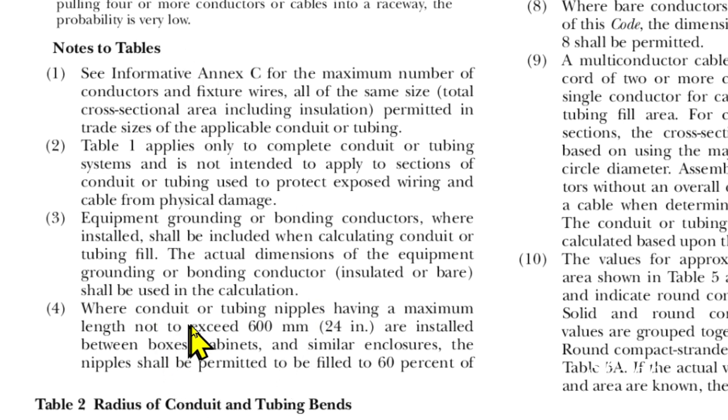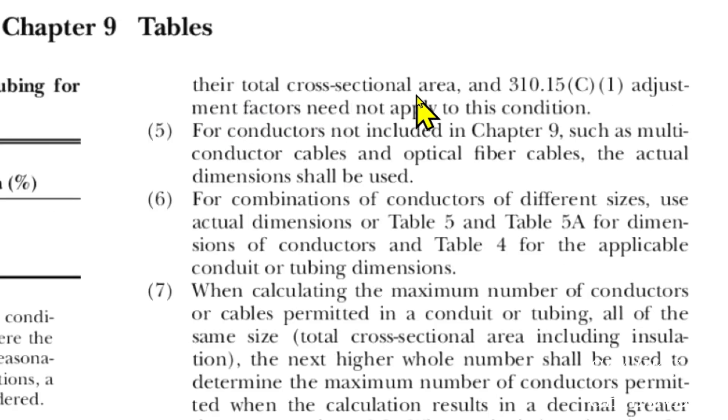We'll go to Notes to Tables, Number 4. It says where conduit or tubing nipples having a maximum length not to exceed 600 millimeters (24 inches) are installed between boxes, cabinets, and similar enclosures, the nipples shall be permitted to be filled to 60% of their total cross-sectional area, and 310.15C1 adjustment factors need not apply to this condition.